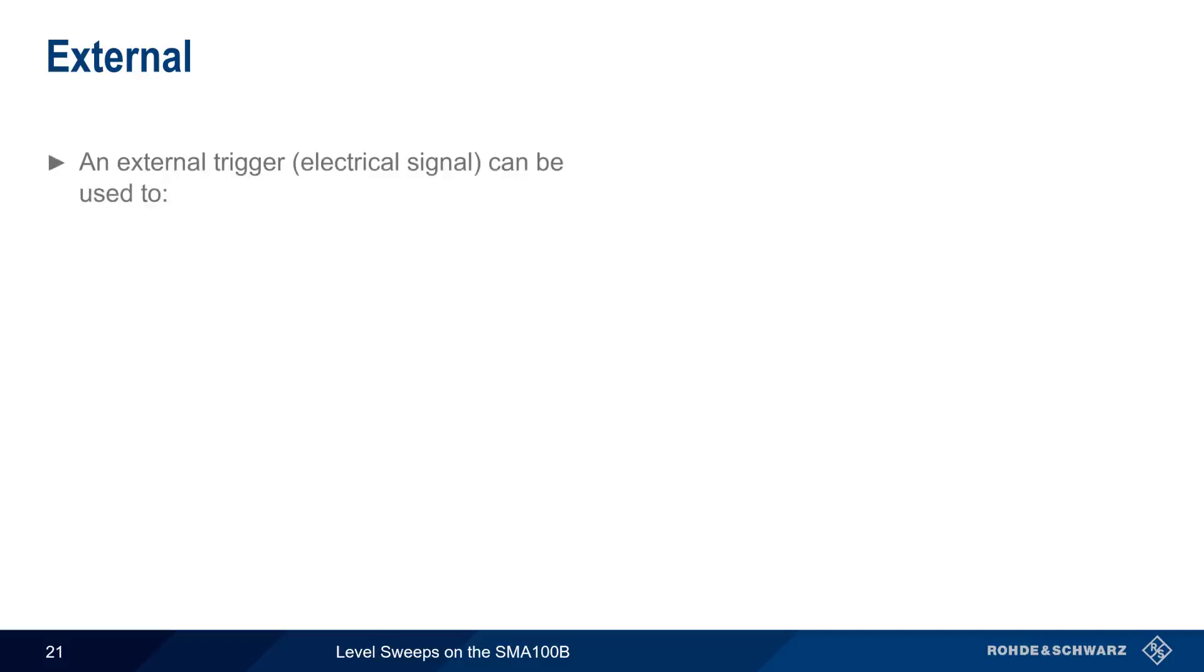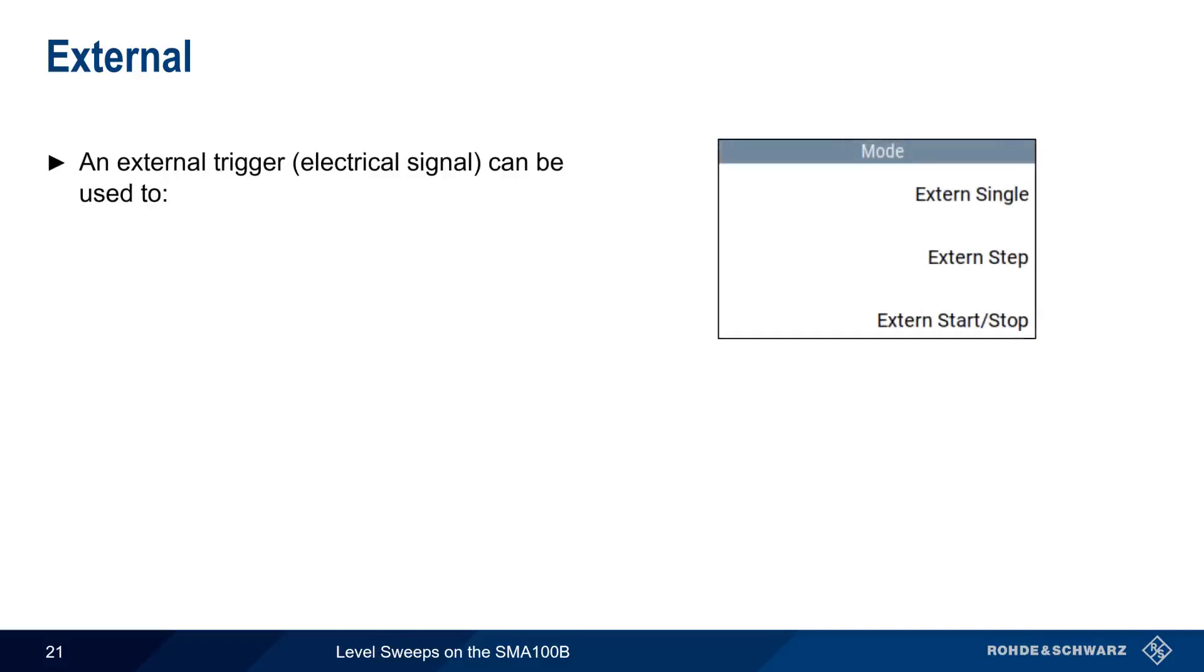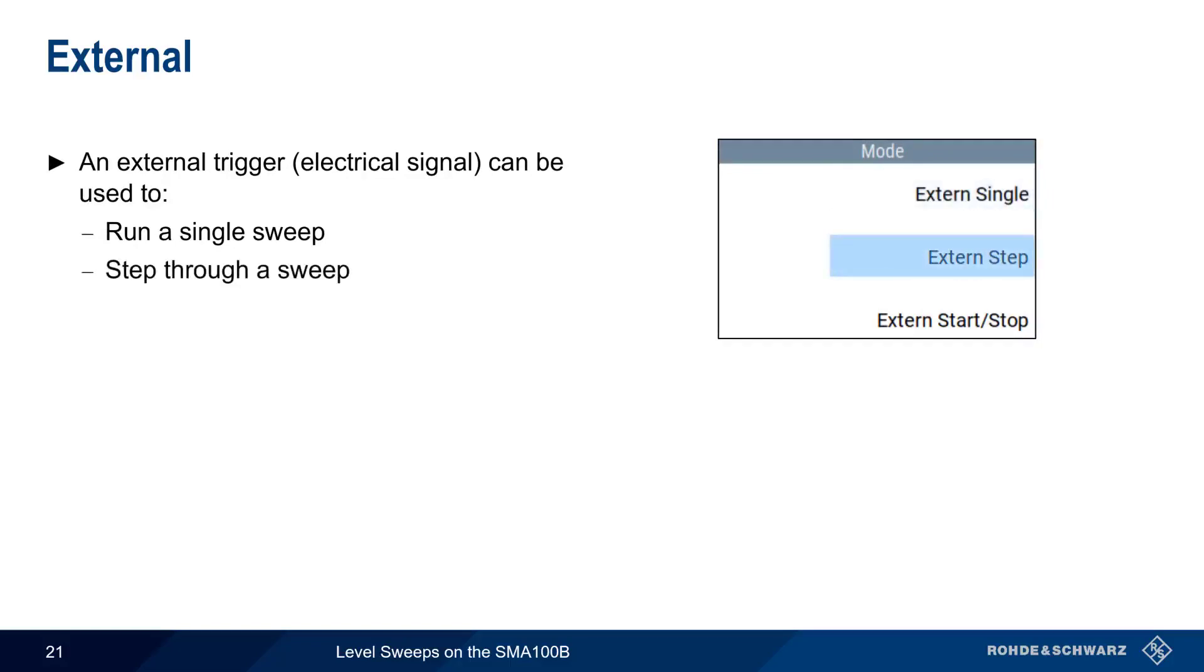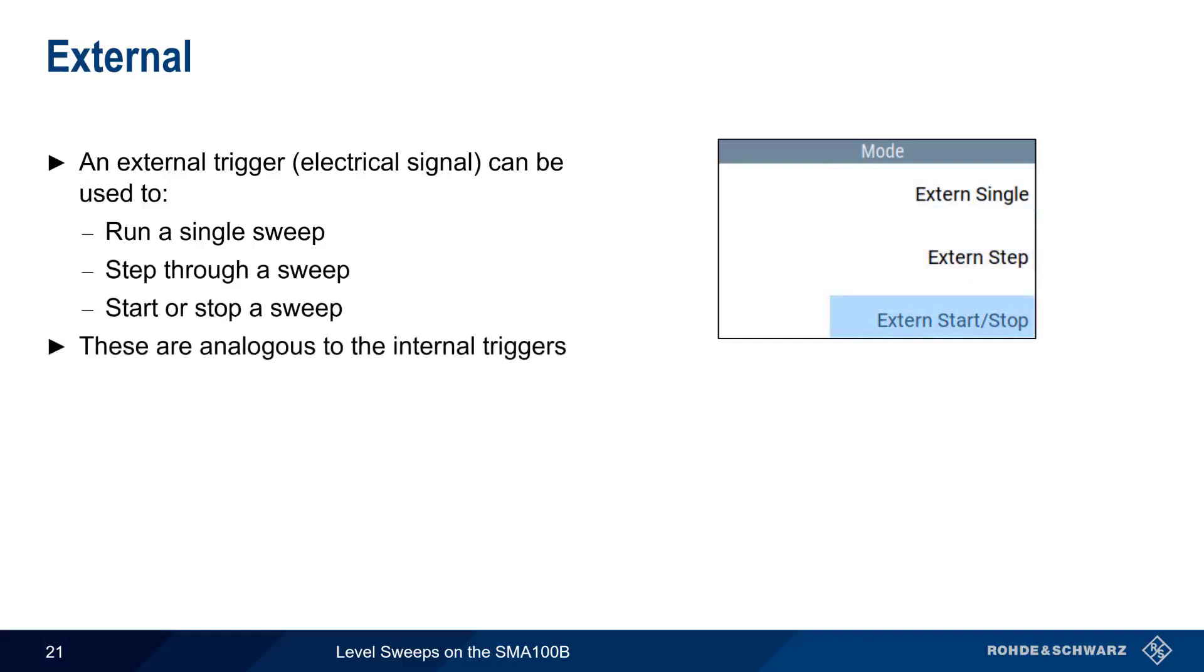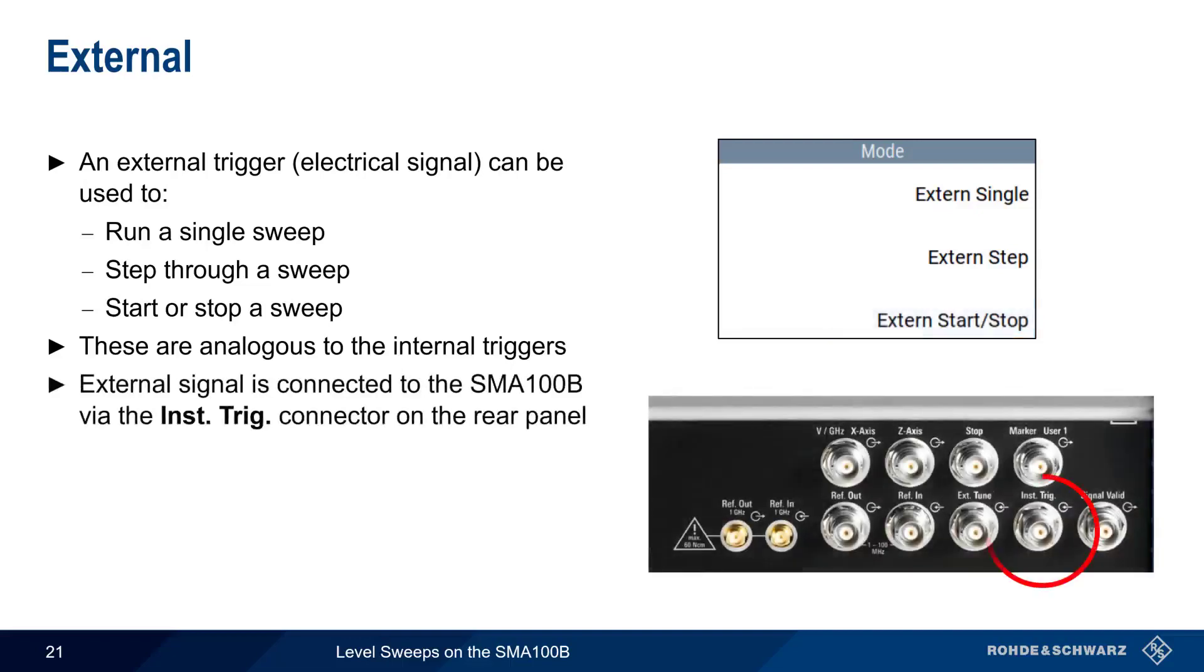Sweeps can also be started using an external electrical signal or trigger. These can be used to run a single sweep, step through a sweep, or to start and stop sweeps. The configuration and use of these external triggers is analogous to the internal triggers we just discussed. The external trigger signal is connected to the SMA via the trigger BNC connector on the rear of the instrument.